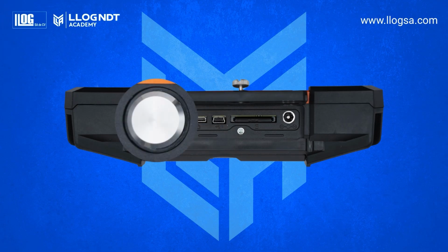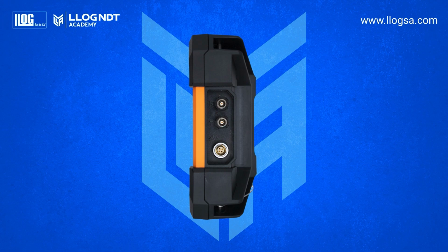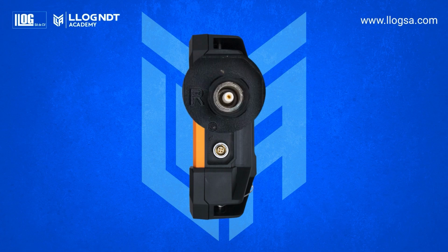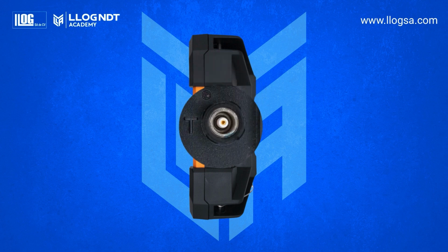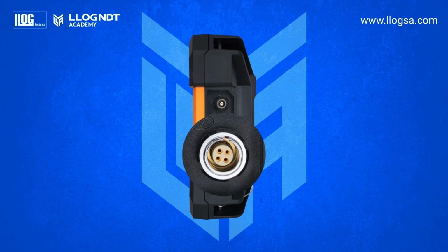Finally, we have a reference block made of steel with a thickness of 4 millimeters, suitable for use with longitudinal waves. On the right side of the device, there are 2 double LEMO connectors. The first is the receiver, marked with the letter R. The second is the transmitter, marked with the letter T. And at the bottom, you'll find the encoder connector, which can be used to synchronize the on-screen scan with the physical movement of the transducer during an inspection.